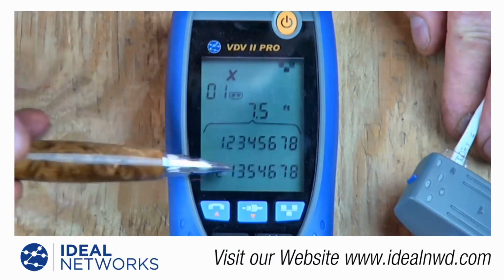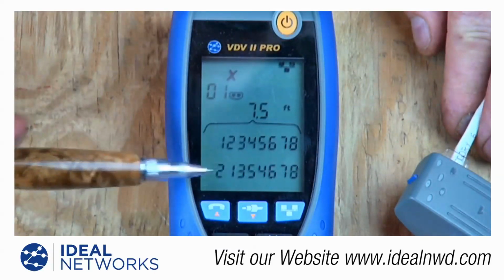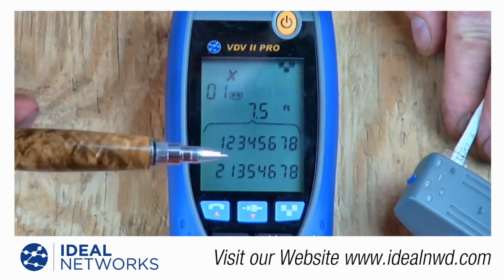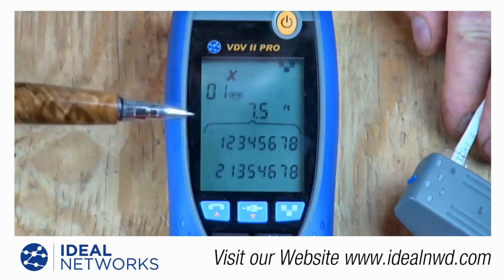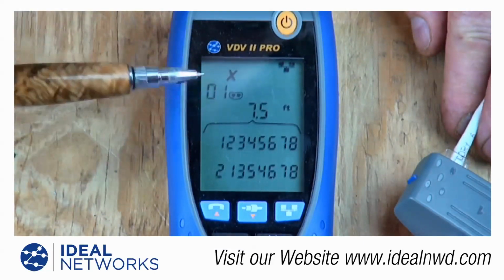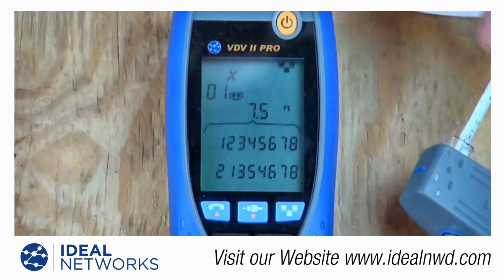That indicates we have a reversal in those pairs. Keep in mind, the reversal could be on either end of the cable. The tester doesn't know which end is miswired, but we do see a reversal in that pair, and again the cable is about 7.5 feet long.